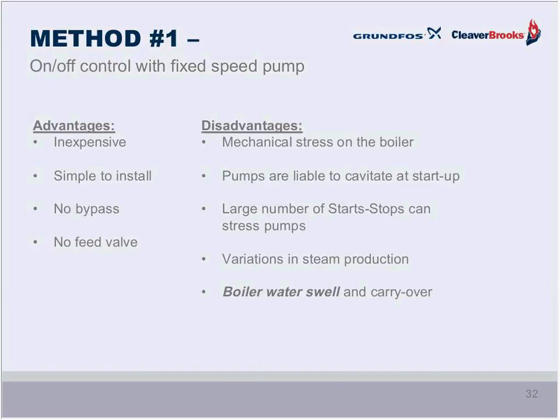Now, there are some advantages and there are some disadvantages to this simple on-off control. It's inexpensive, it's very simple. There's no bypass valve, which, you could argue, wastes flow, and there's no feed valve. And there's pretty significant pressure drop across the feed valve, and pressure for a pump equates to energy consumption. The higher the pressure loss in the system, the greater the horsepower required, the more kilowatts, and that results in higher energy consumption and higher costs for power.